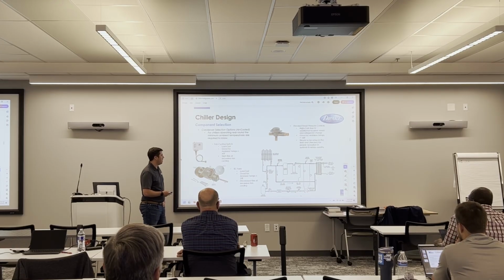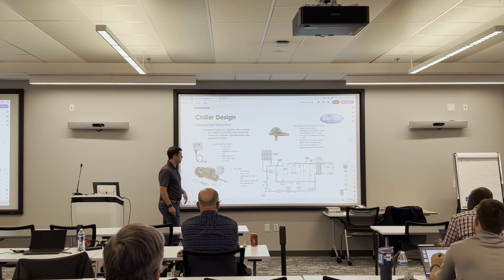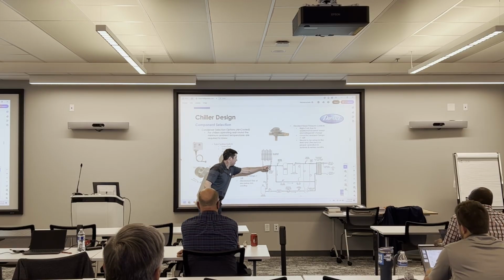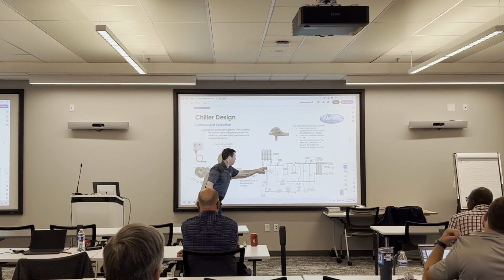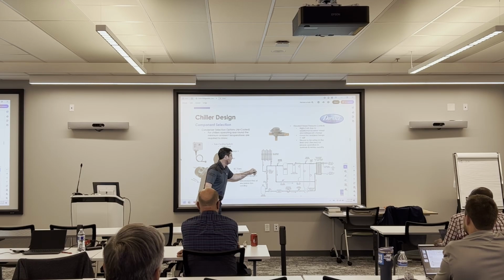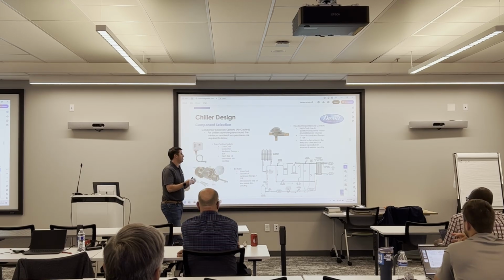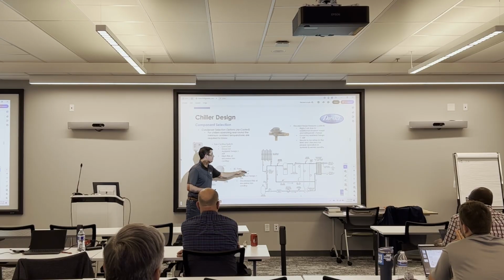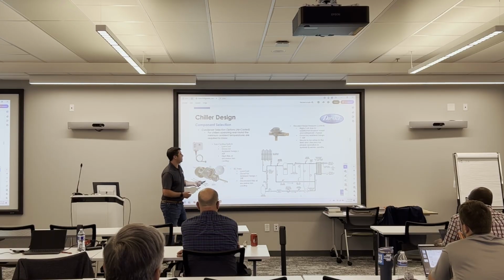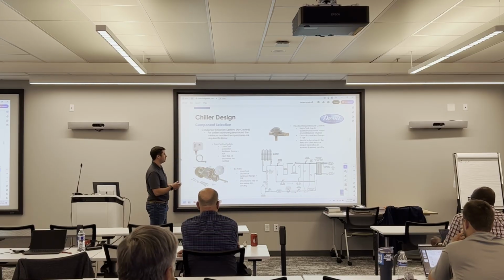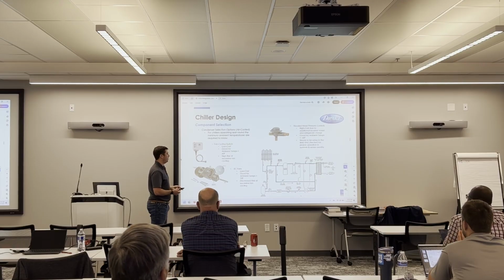So your head pressure valve, in this case, has 3 ports. It's got one port from the discharge line coming off the compressor, if you wanted to bypass the condenser coil when it's really cold outside. And then we have our condensing port right here, which will actually restrict itself to kind of, I call it, stacking liquid. It essentially decreases the surface area of that coil in the winter time, and builds head pressure ultimately.